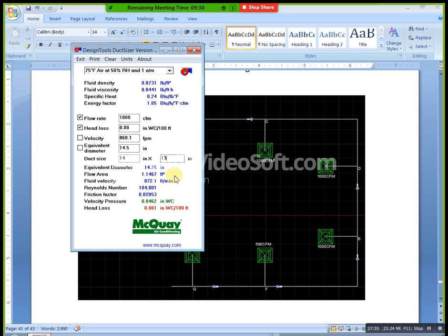If you do any fabrication duct work or follow any standards, such as SMACNA standards, we always take even numbers. You don't consider odd numbers in duct sizes. Odd numbers are not applicable when you calculate your duct sizes. Then you will take directly 14. 14 by 14 is the exact aspect ratio.